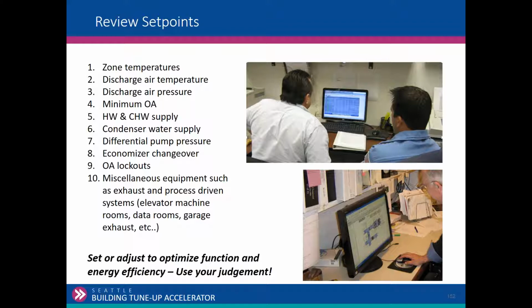What kind of economizer are they using? Dry bulb, enthalpy, differential dry bulb, differential enthalpy? And are the set points correct? Outside air temperature lockouts. Anybody had a boiler enabled when it's 80 degrees outside? Or a chiller enabled when it's 50? Right?